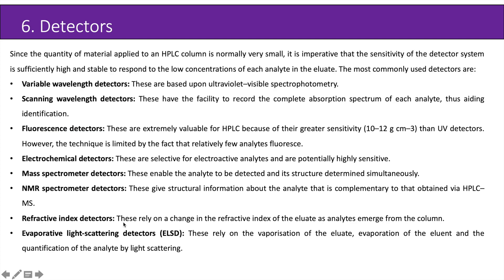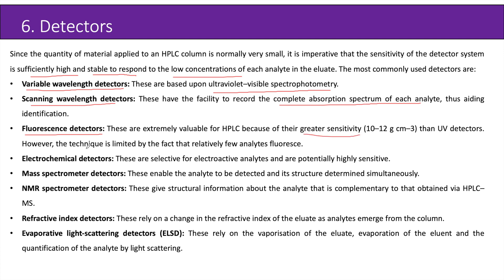Next are the detectors. Since the quantity of material applied to an HPLC column is normally very small, it is imperative that the sensitivity of the detector system is sufficiently high and stable to respond to the low concentrations of each analyte in the eluate. The most commonly used detectors are: variable wavelength detectors, based upon UV-visible spectrophotometry; scanning wavelength detectors, which have the facility to record the complete absorption spectrum of each analyte, thus aiding identification; and fluorescence detectors, which are extremely valuable for HPLC because of their greater sensitivity than UV detectors, though limited by the fact that relatively few analytes fluoresce.